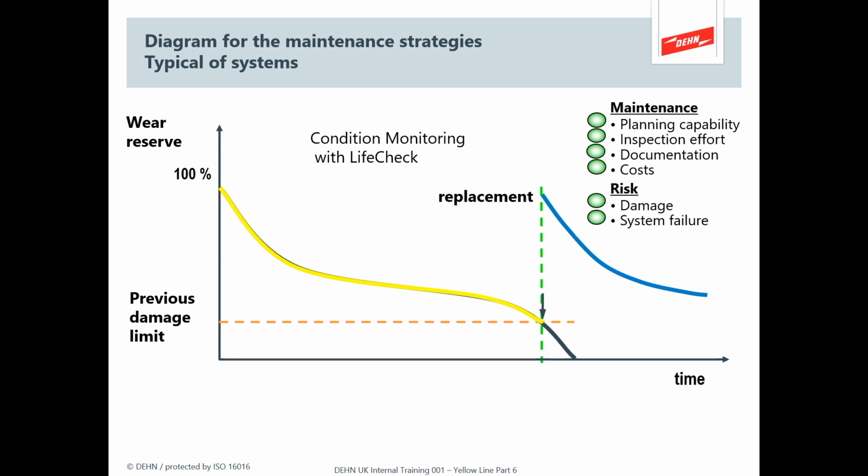So now we don't wait for things to go bang. We actually have a more preventative sort of thing. So if we detect that one of the SPDs is beginning to fail, which we would detect, there would not be any damage because we replaced the SPD before that damage can happen.